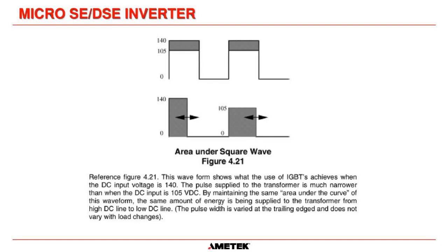And the reason we do that is you've got to remember always that we have a battery, and we've got to design our inverter to work at both ends of what the battery is going to see. So at the highest end, on a 60-cell system, is going to be 140 volts. That's the equalized voltage of most lead-acid batteries.